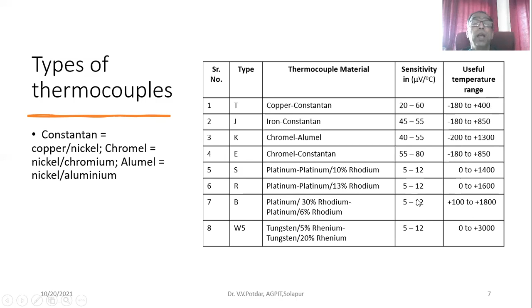Now, on what factors is the selection of thermocouple dependent? Quickly, we'll see criteria for selecting a thermocouple. What is the temperature range that I want? What is the chemical resistance of the thermocouple or the sheath material? What is the abrasion and vibration resistance? And what are the installation requirements? May need to be compatible with existing equipment. Existing holes may determine probe diameter.